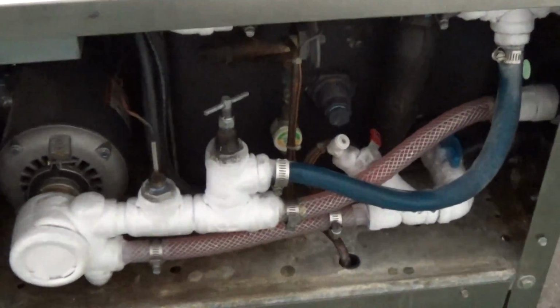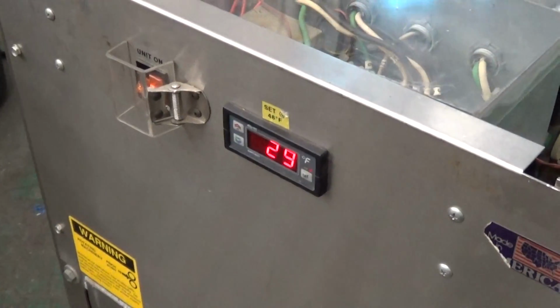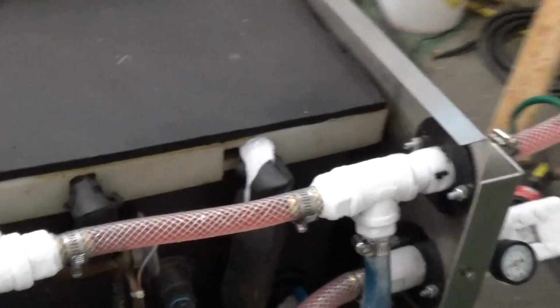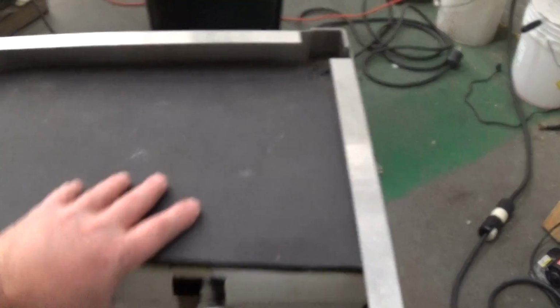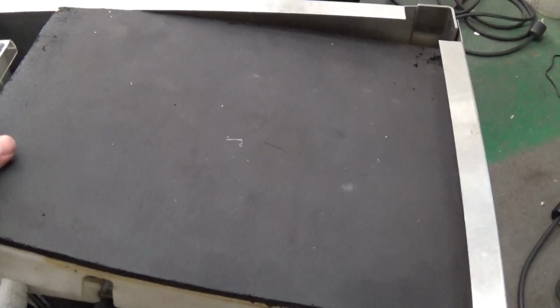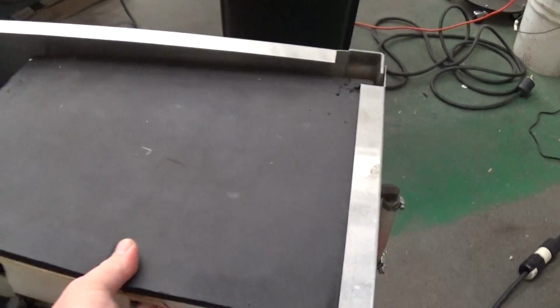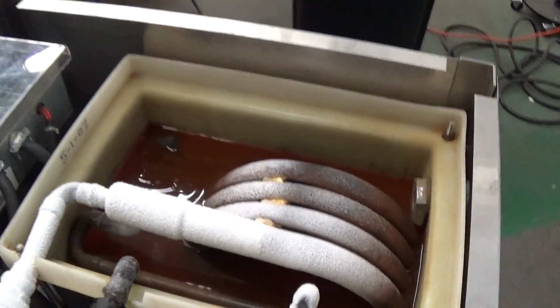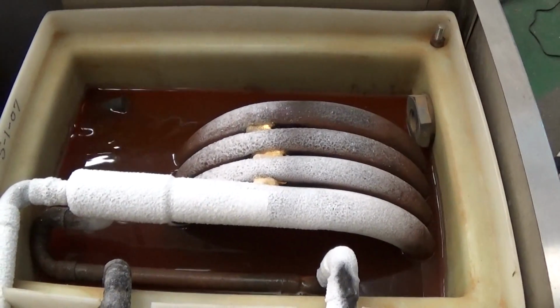before the unit ships. So it's got a little 1.5 horsepower compressor actually down below here where we have the fans. You can just see a little refrigerant dryer there. Again, the unit is chilling right now. That was our air compressor in the background, sorry about that. It's got a very basic in-tank coil exchanger. And we're running about a 30% glycol mix.